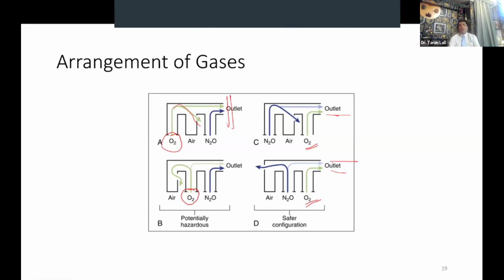So suppose we have this arrangement A, where I'm giving oxygen 1 liter and nitrous 2 liters. But from here, 500 ml of oxygen is leaking out. So by the time the mixture is formed, the patient gets only 0.5 liter of oxygen, but has got 2 liters of nitrous. I wanted the ratio 1:2, but the patient is getting the ratio 1:4. But in the last arrangement, suppose I have used the same flows. Now, if there is a 0.5 liter leak, both nitrous and oxygen are being lost, so my patient will not get a hypoxic mixture. So the thing to remember is that oxygen should always be downstream of all other gases.